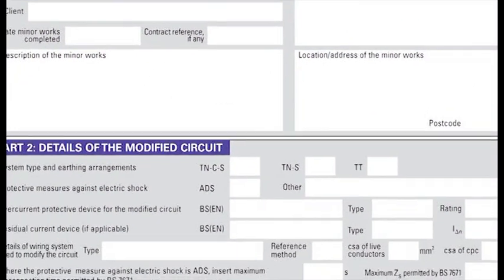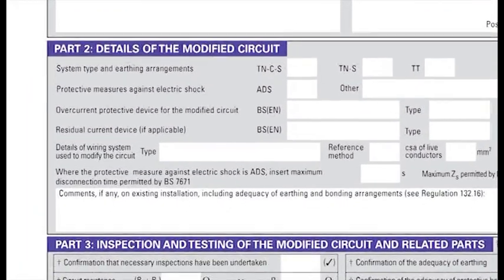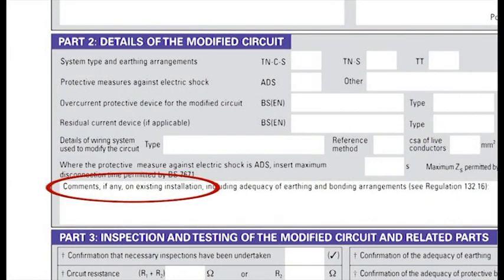Yes, this is one of those cases where allowance is made by the regs as long as it can be proved that the equipment installed is no less safe than similar equipment which does meet the required standard. It's more common for comments on the existing electrical installation to be placed in the big box under details on the modified circuit.